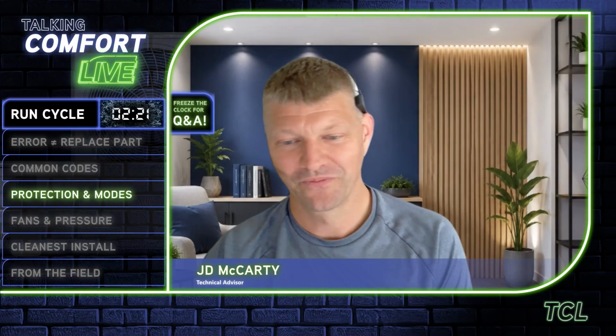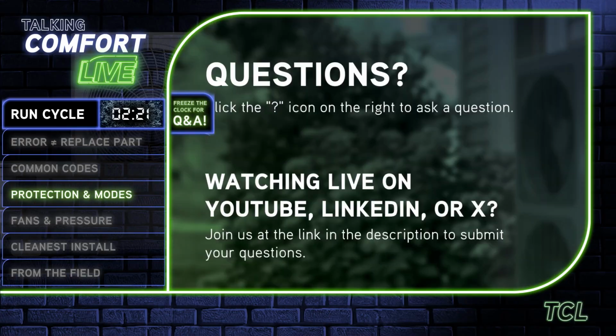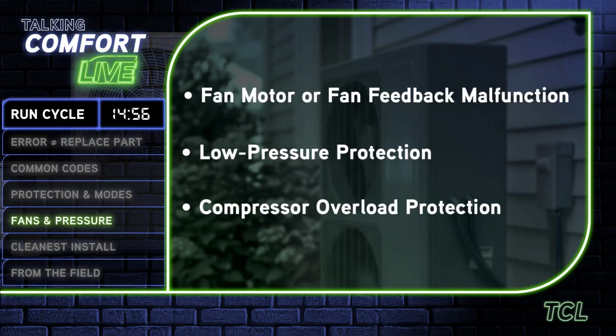All right. Well, y'all ready to move into the next segment here? Fans and pressure. Yep. All right, so let's finish it up with 3 additional faults: fan, low pressure, and compressor protection faults. So fan motor or fan feedback malfunction, that is an H6 commonly.